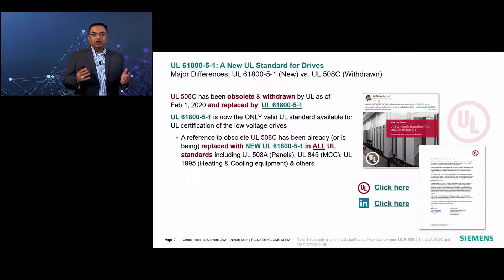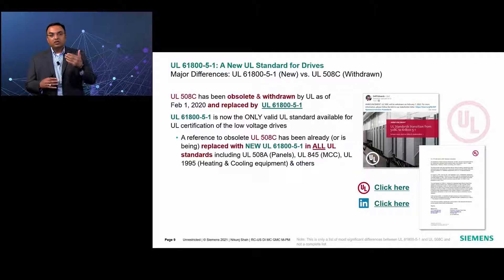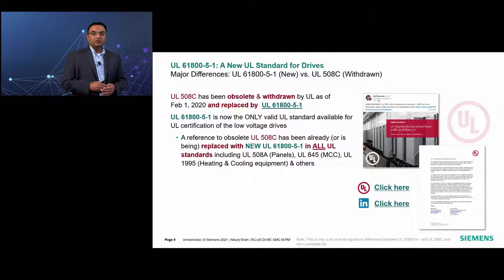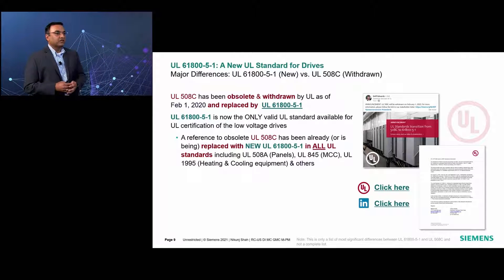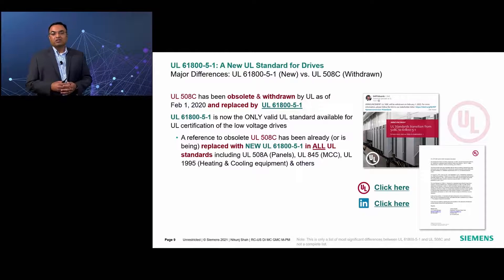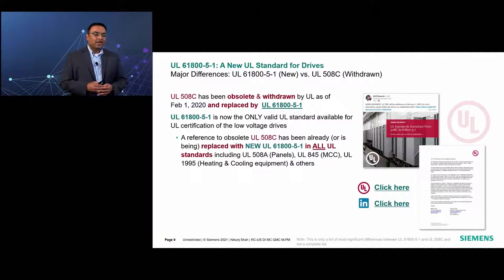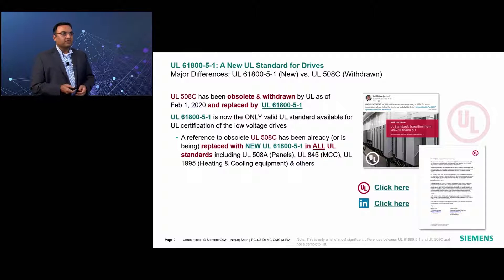There are about 80 active UL standards where 508C was referenced, and UL has started replacing those references with the new UL61800-5-1 in all those standards, which include the standard for industrial control panels (UL508A), standard for motor control centers or MCC (UL845), for heating and cooling equipment (UL1995), and others. Here is the link showing UL notices to manufacturers about this withdrawal of references.